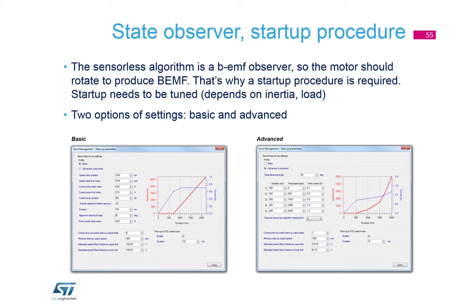That's why we created the advanced startup, which allows up to five steps where we can play with currents and speeds — including negative current or negative speed. For a pump/compressor, you can turn and align the motor backwards: instead of pushing against high pressure, you release pressure by moving the piston backwards. Then when you start the real acceleration, you face much smaller pressure, and once you gain enough inertia you can overcome the highest pressure peak. The advanced startup helps in situations where startup would otherwise be too heavy.